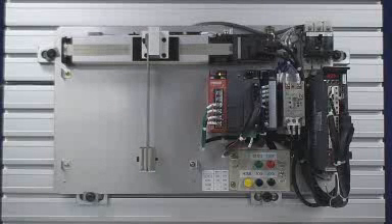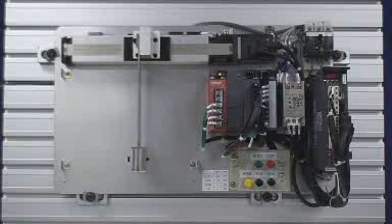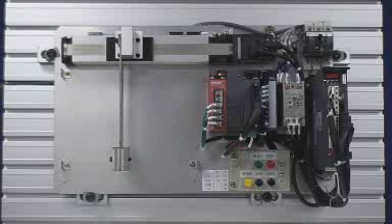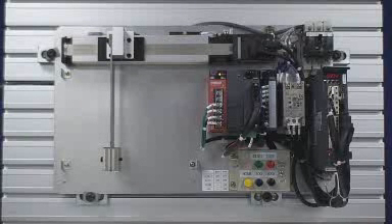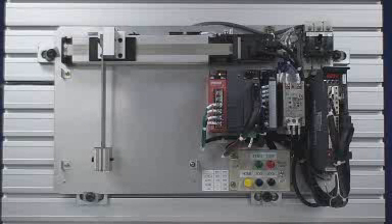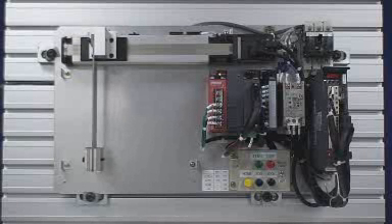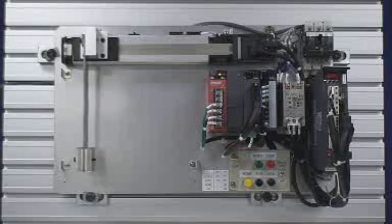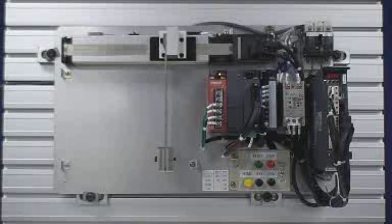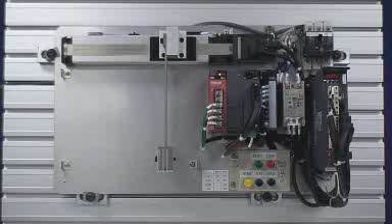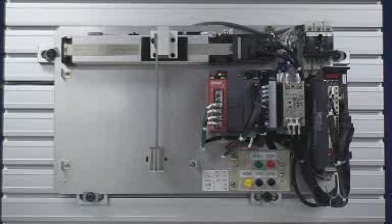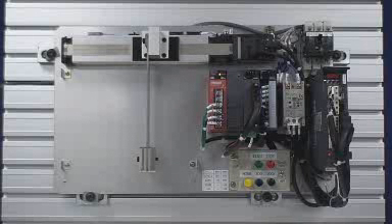In addition to this vibration control, the J3 servos have an adaptive filter that automatically optimizes the machine resonance suppression filter, and also robust disturbance compensation function that helps keep the motion smooth and multi-axis systems synchronized.